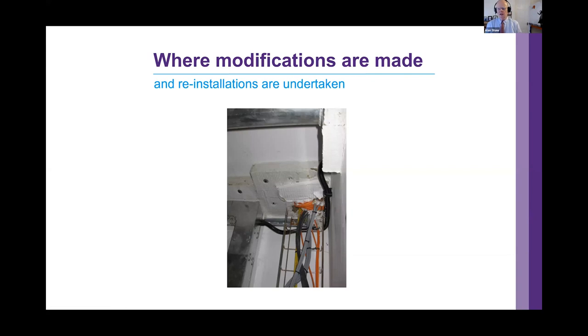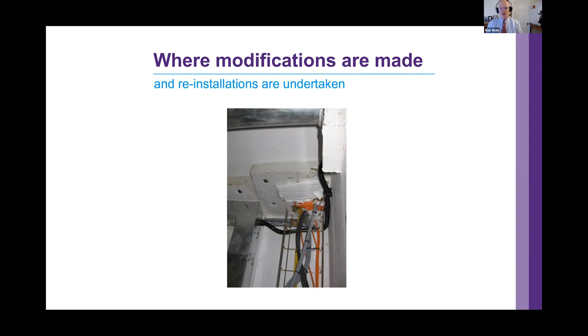It's smaller and electrical, but they've still stopped it — passive fire protection. Where changes are done to cabling and pipework, fire stopping may be perforated like new repairs, so they need to be made good if you've cut through the compartmentation. The records must be updated, and the accompanying certification labels updated. Take photographs, because that's evidence of due diligence in a court of law.